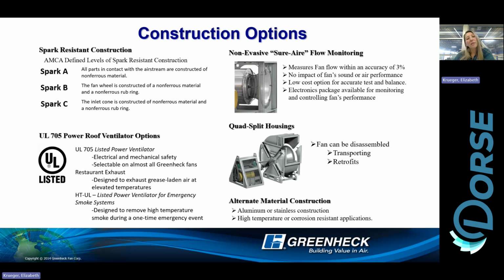I have spark resistance listed also. Spark resistance is not the same thing as an EXP motor. We're not talking about explosion proof here. We're talking about the airstream actually being non-ferrous, so non-sparking. So we actually will make parts of the airstream, if not the entire airstream, out of aluminum.